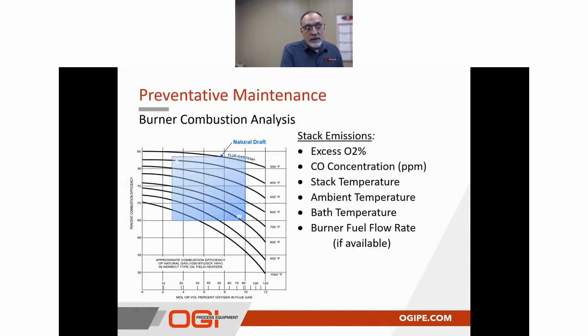After we've gone through that and we've got a decent pilot operation and a main flame that's working properly, we want to go ahead and evaluate the burner combustion and make sure that the performance of that burner is in good shape. So at this point, what we like to do is allow the main burner to run for about 5 to 10 minutes and then conduct a stack emissions test after the stack draft has been properly established. So here, as you can see, we're going to take a look at any excess O2, the CO concentration, and stack temperature. We're going to compare those to the ambient temperature and the bath temperature. And if available, we're going to measure the fuel flow rate.